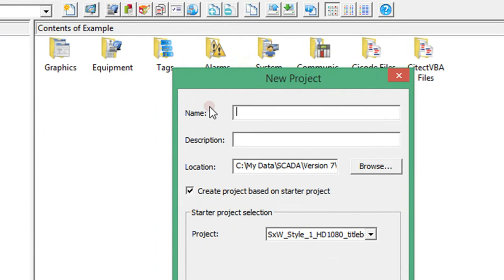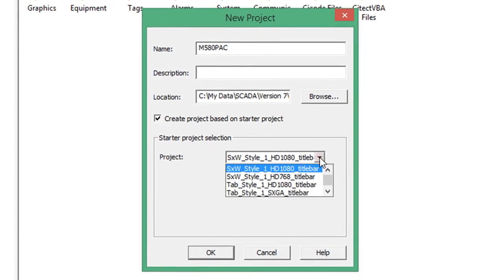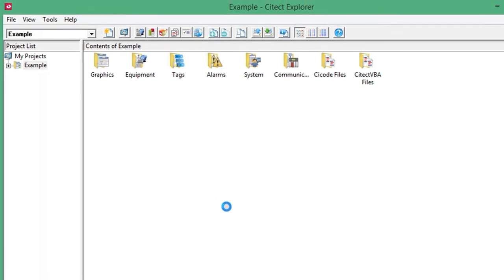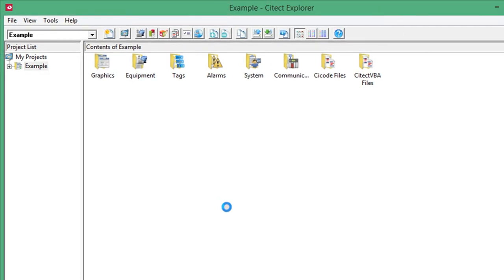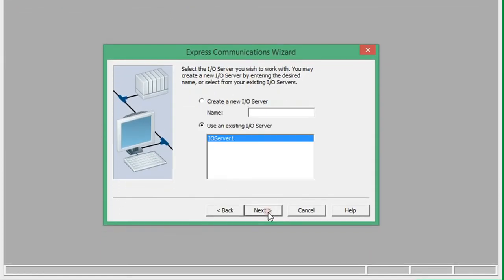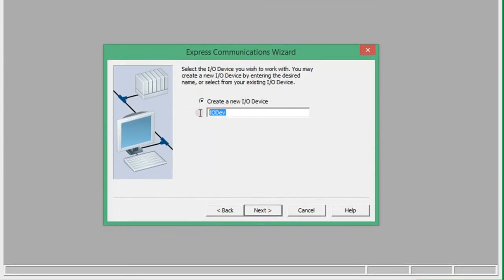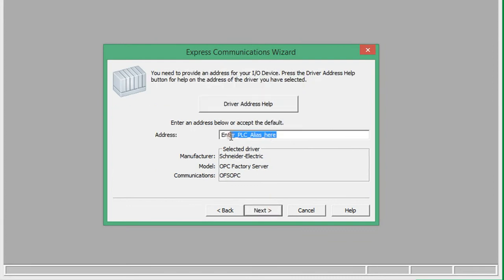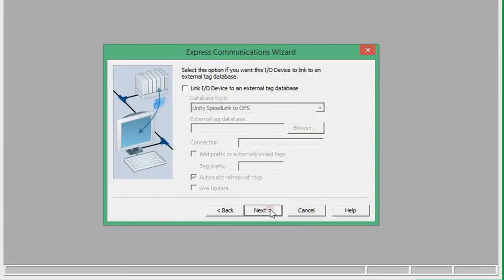The next step is to set up a Citect project. I will create a project called M580 and select to use the starter project for the StructureWare widescreen 768 layout. Once it is created, next is to add an entry for the external I/O device in Citect. This can be done using the Express Communication Wizard. I will use the existing I/O server and create a new I/O device — an external device that will use OFS as the communication source. Here I will enter the name that was created in the OFS configuration and then finish the setup.